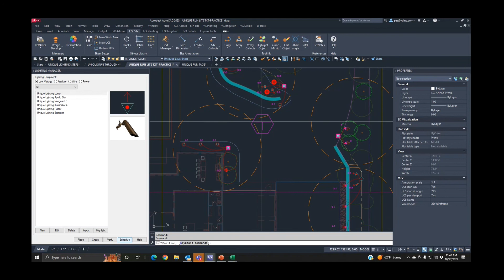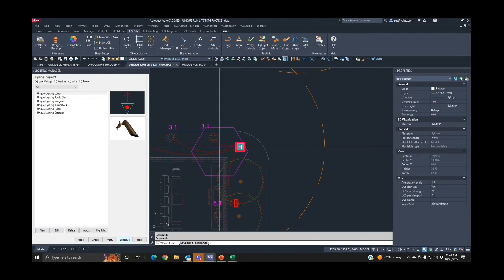Okay, back to where we were - we're setting this custom callout for each one of our hubs. We'll set this callout right next to our hub, and this little block has some attributes associated with it. It's asking what transformer number we're going to - right now we only have one transformer, so we'll say number 1. Then it asks for our total wattage on this IntelliHub. We have our numbers right here for VA: 3.1, 3.1, 3.1, and 5.3 - that's 14.6. Then it asks what run number - this will be run number 1. So we just set our tag.